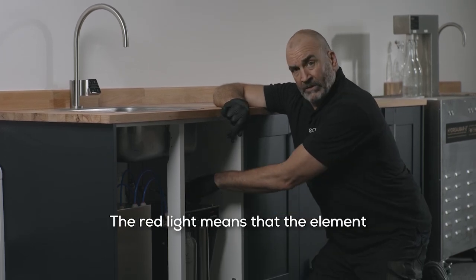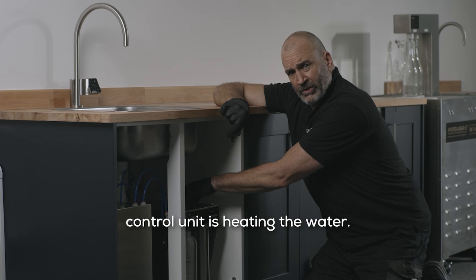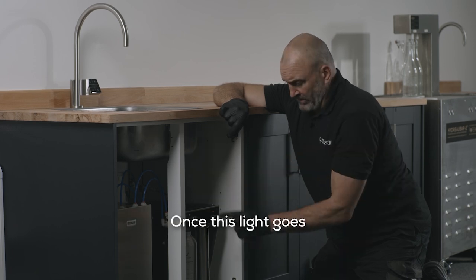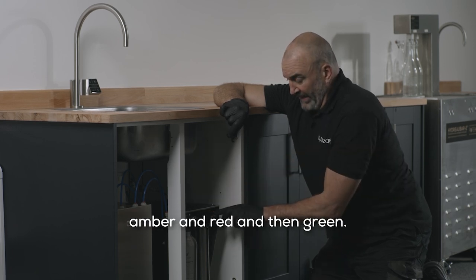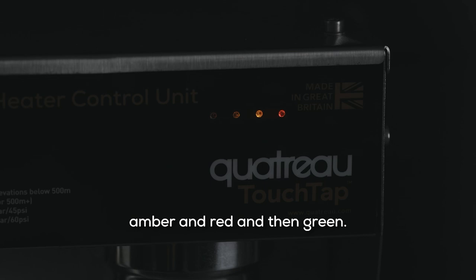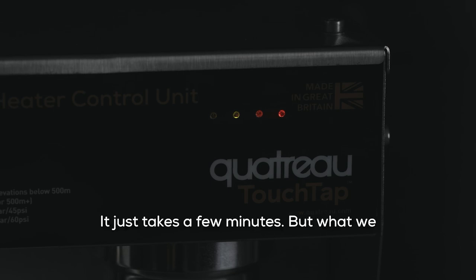All we have to do now is on the front of the system, the red light means that the element inside the water heater control unit is heating the water. Once this light goes amber and red and then green, as soon as it goes green and stays green, you know that the water's hot enough to be able to test it. Just takes a few minutes.